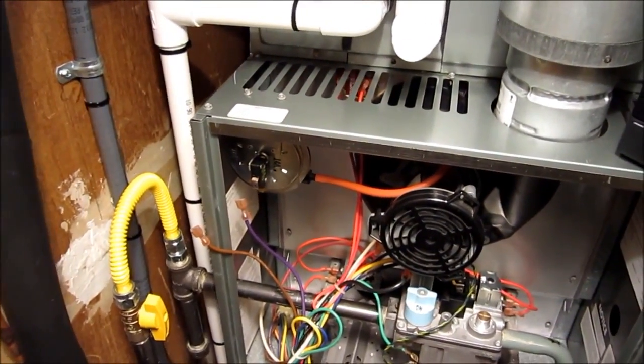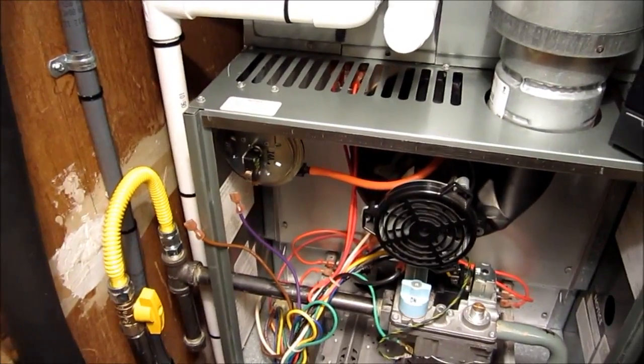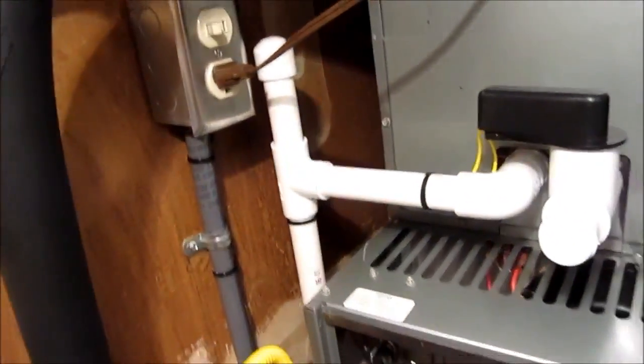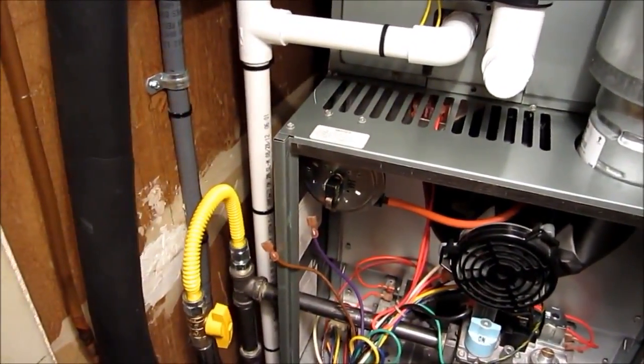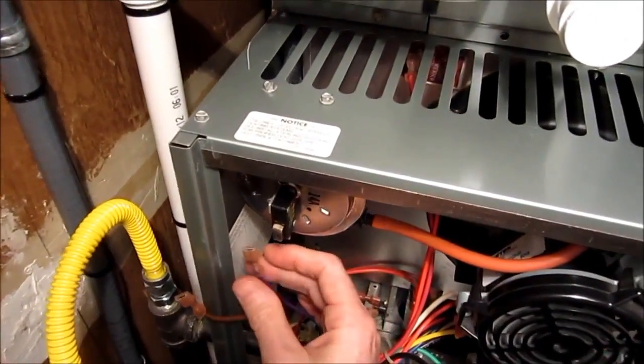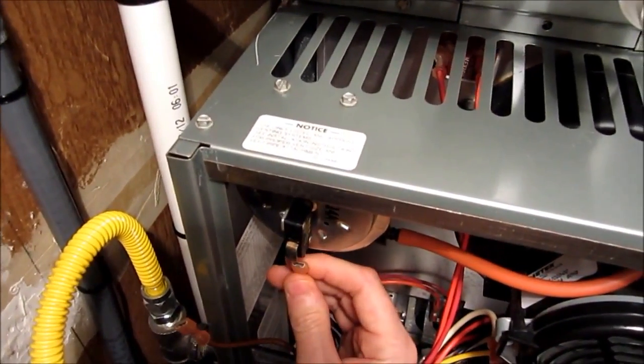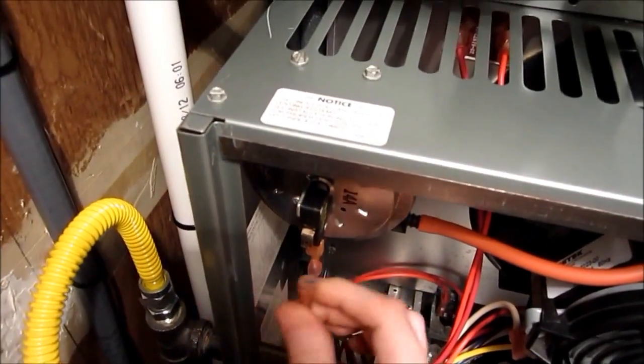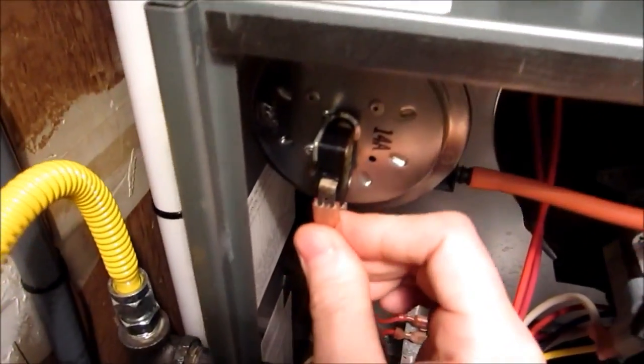All right Ray, let's move on to another electrical test we can do real quick. The power is still off, correct? Yes. Go ahead and take your respective wires to your respective terminals and leave me just enough to get your alligator clips on there. What we're actually doing here Ray, is we're going to check for a closed pressure switch during a call for heat.